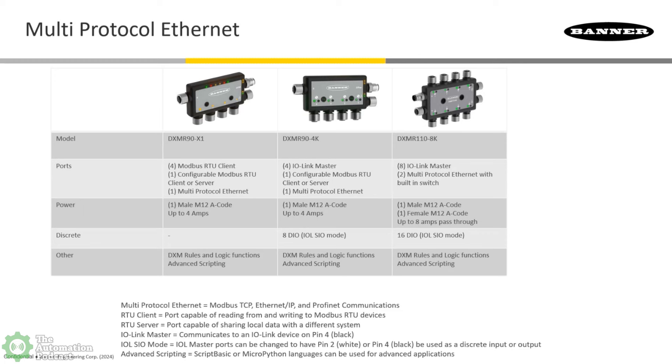That's a great point — it saves so much time, and time is money. I've also seen with diagnostics where a machine would be down and they're trying to figure out what's going on, and it turns out it's something as simple as a screw terminal not tightened down enough. That could be eliminated with the connectivity with Remote I/O. I'm raising my hand on that because I've driven five hours just to solve that problem. You didn't screw down the screw all the way. I've been in that position. It happens for sure.